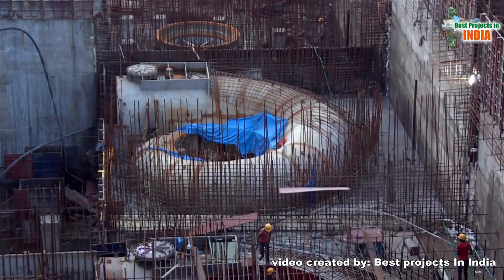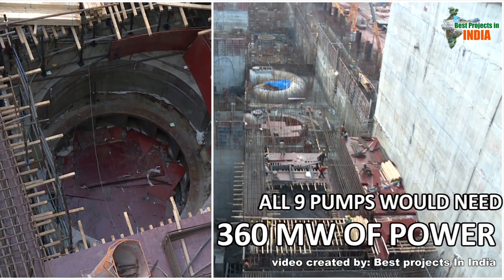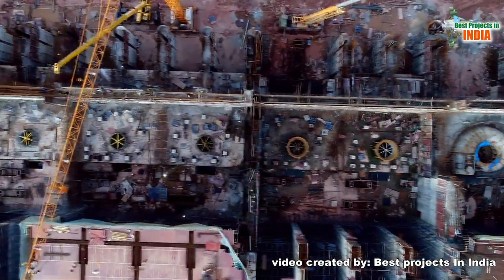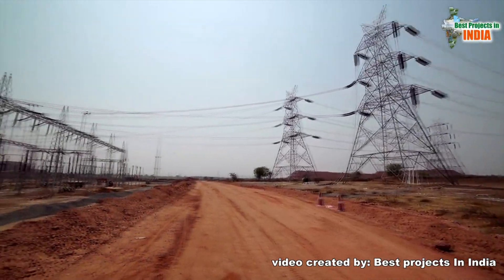Each pump of Sundilla Pump House requires 40 megawatts of power. Together, all nine pumps would need 360 megawatts of power. To facilitate uninterrupted power supply to the pump house, a 400 kV substation was built, he said.